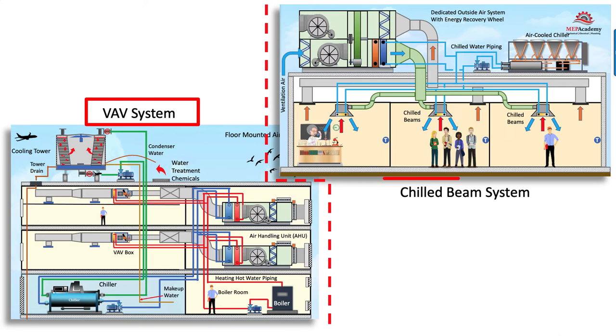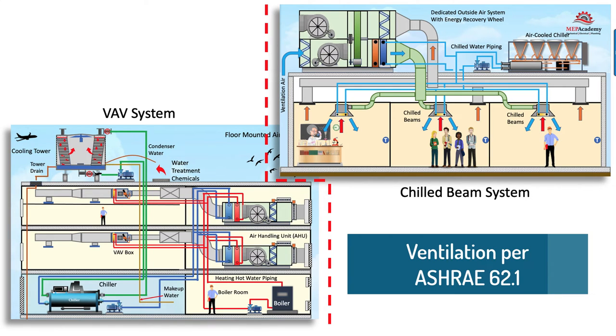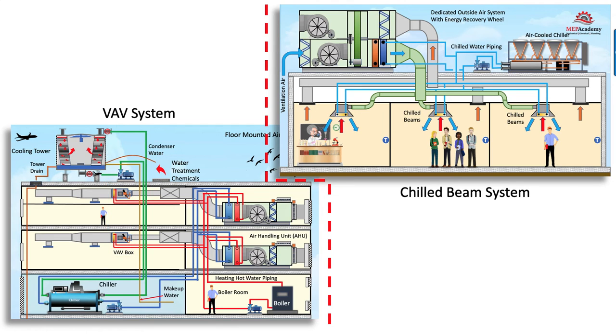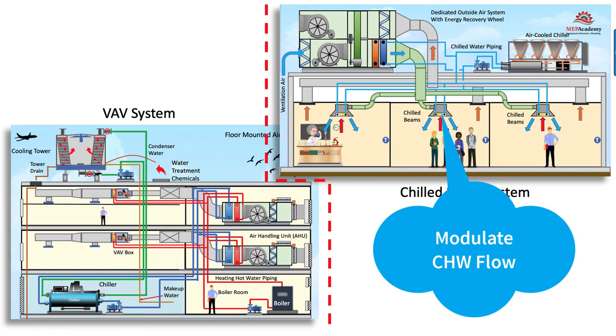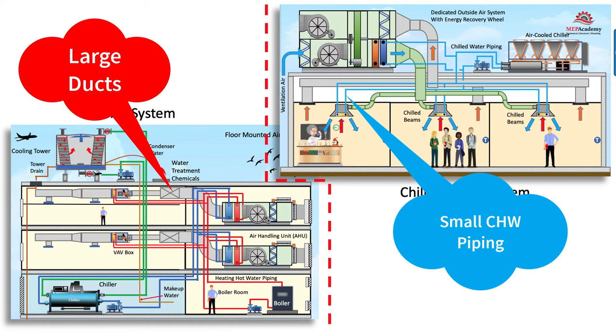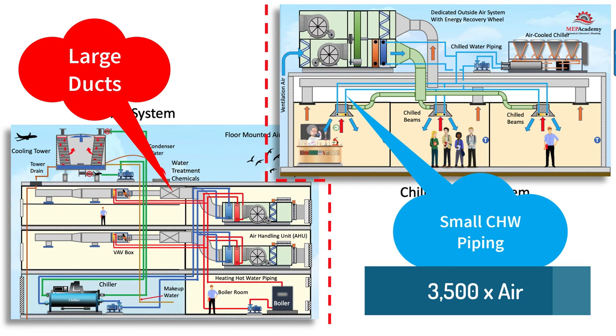Comparing a VAV system to a chilled beam system: all occupied spaces require ventilation air per ASHRAE 62.1, but using reheat in a VAV system to control space temperature is less efficient. The VAV system will reheat air that has already been cooled to maintain space temperature, while the chilled beam system modulates water flow to the coil to respond to low demand without the wasted energy of reheating. Chilled beams use a constant volume of air, while the VAV system varies the quantity of air to the space. Instead of delivering cold air through large ducts, the chilled beam system uses the more energy-efficient carrying capacity of piping — chilled water piping carries over 3,500 times the volumetric heat capacity of air ducts.